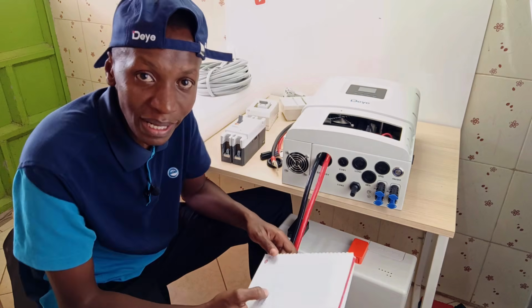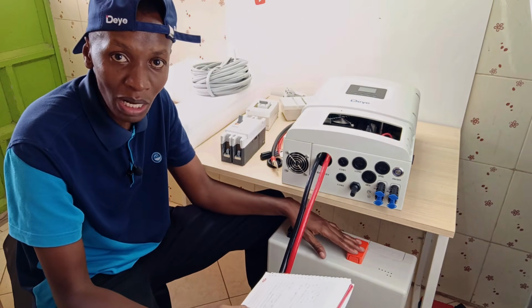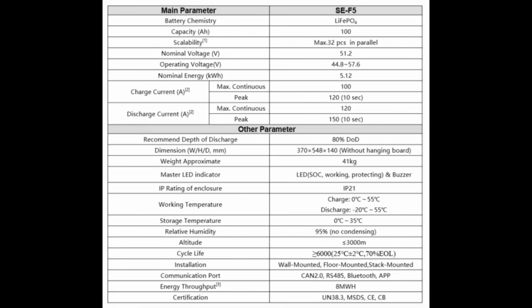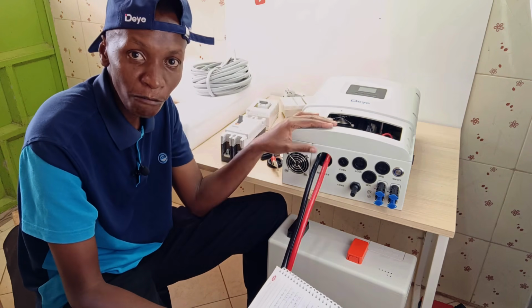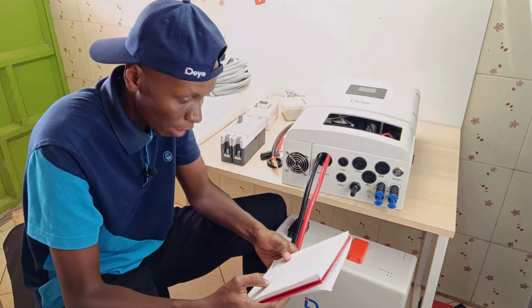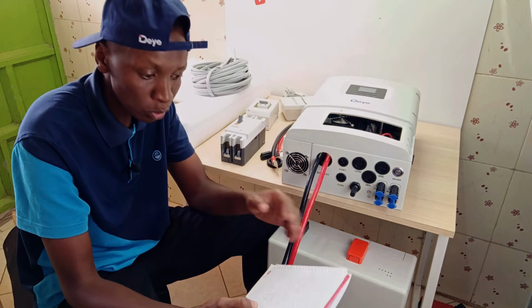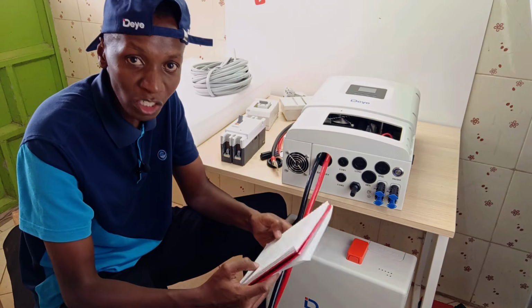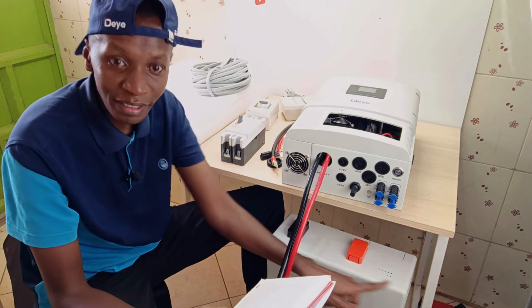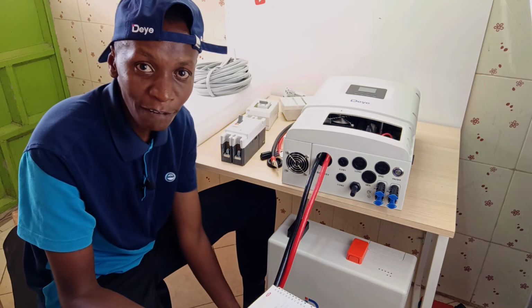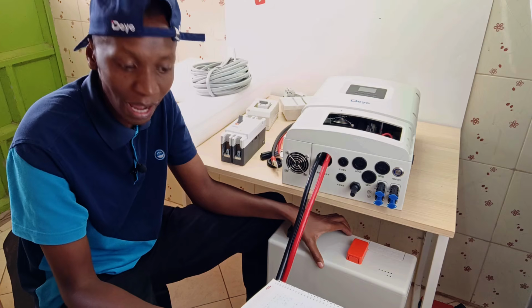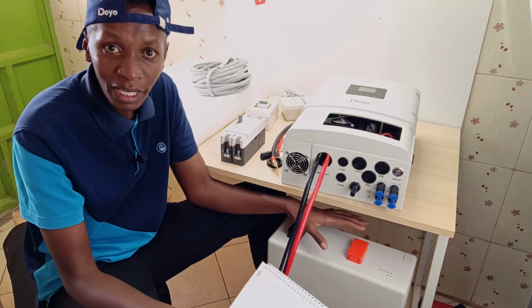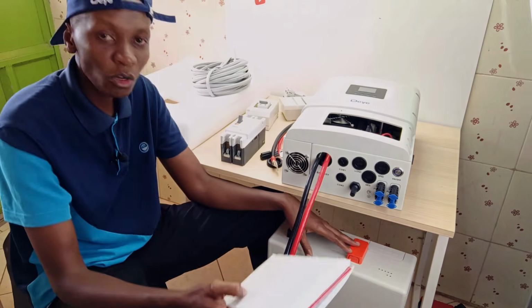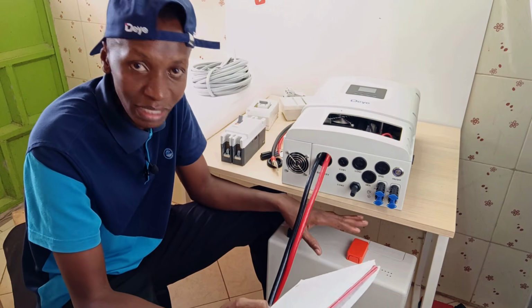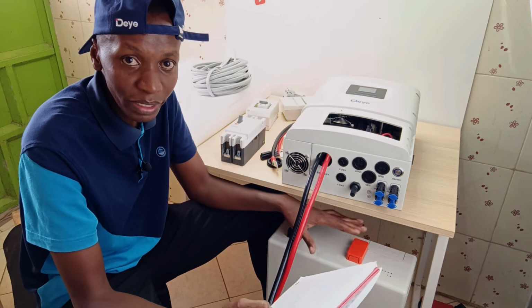And now let's talk about the battery specifications. The voltage is 51.2 volts, but the operating voltage is between 44.8 to 57.6 volts, which is less than the maximum of the inverter, which was 60 volts. Now it is a 100 Ah battery, and if we multiply those two together, we get 5.12 kilowatt hours nominal energy. The dimensions are 370 millimeters wide, height of 548 millimeters, and a depth of 140 millimeters. Now you can connect this unit in parallel with other units, and it has over 6,000 cycles at 80% depth of discharge. So this thing will last you years and years.